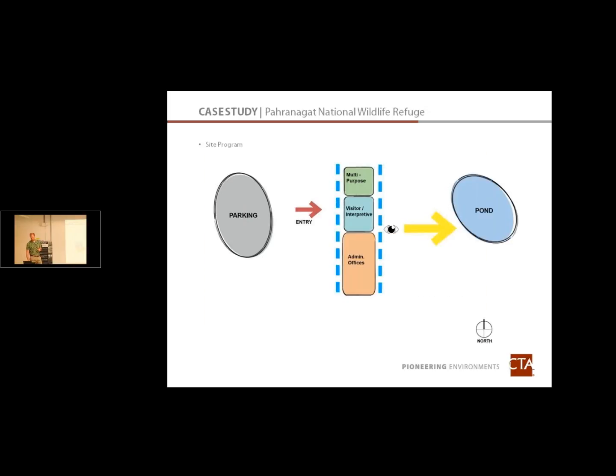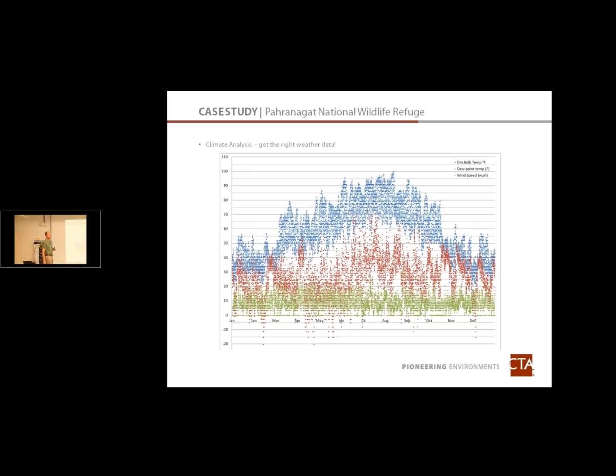So at this point I start looking at the weather, and this was the example of a TMY3 set. I just found the closest TMY3, typical meteorological year. They've got 1,000 locations around the country or something. And it was 90, 100 miles away, and it was way off. The peak temperatures were 110, 115, and it never got below freezing. But just 100 miles away, we were in the high desert, kind of out of the Mojave Desert, and it really cooled down quite a bit, ended up being a lot like the Boise climate. So early on we made a few assumptions that were incorrect and had to go back and fix that.